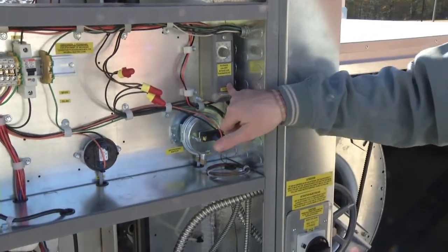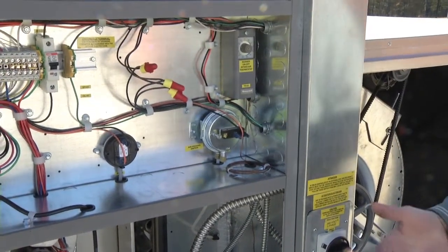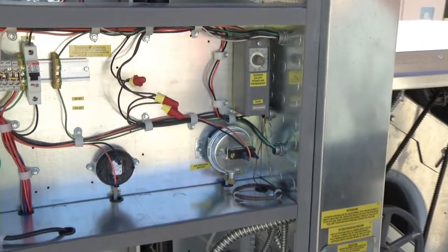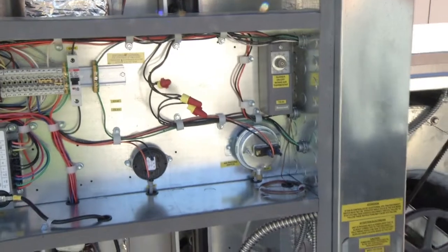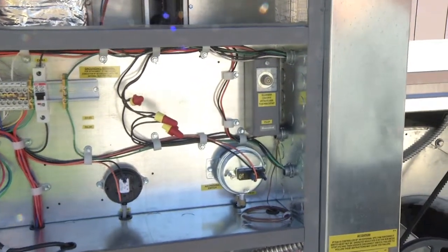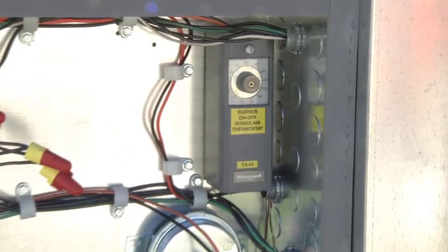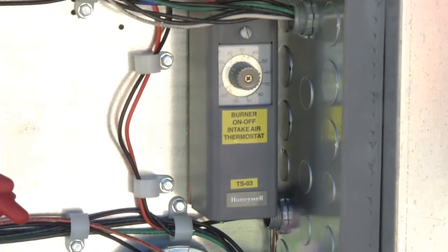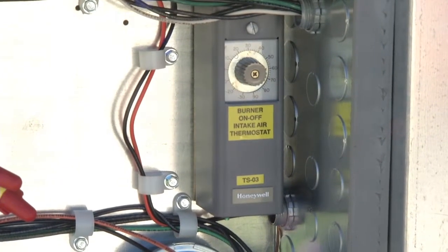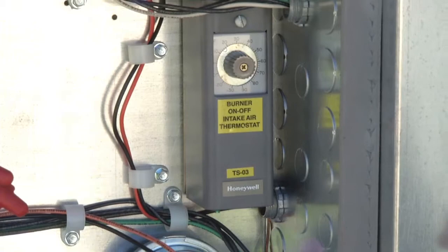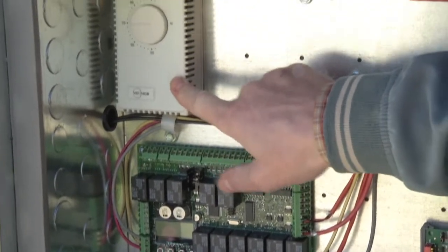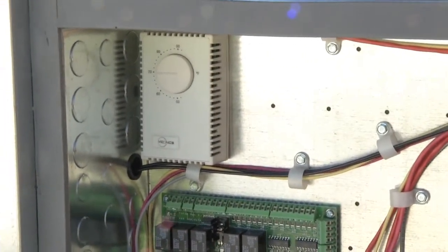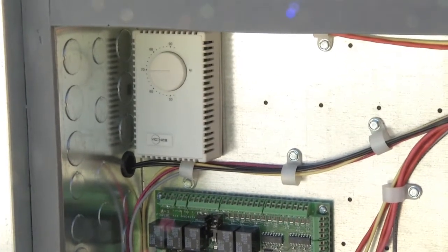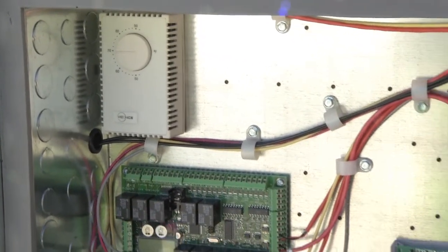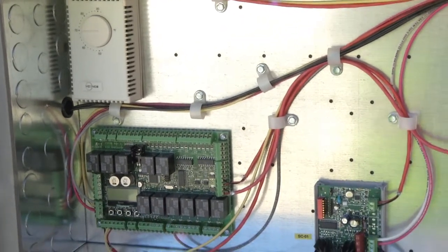Further back are the controls for this heater. First, we have the intake air thermostat. This is what tells us what the temperature needs to be outside before it tries to turn on. In this case, it's set for 60 degrees Fahrenheit. So if the outside air temperature is 62 and the kitchen staff says, hey, I feel cool air coming in, it's because it's delivering 62-degree air. It's not going to fire the heater until it drops below 60 degrees. On the opposite end of the unit is our discharge air thermostat, currently set at 70 degrees. So whether it's 55 degrees outside or 35 degrees outside, the discharge air temperature will be 70 degrees on this unit.